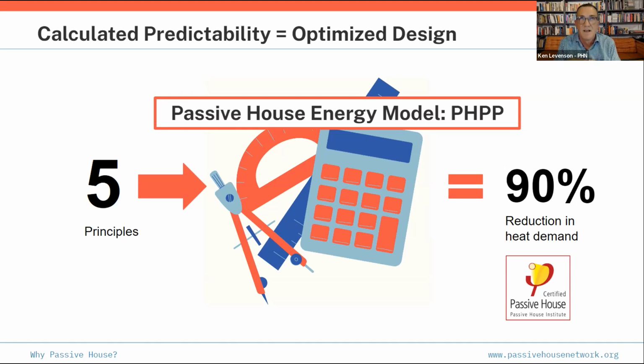We often see the heating and cooling reduced dramatically. When I was practicing architecture, one notable example was a house I was working on in Brooklyn Heights. All the neighbors had 12 to 15 tons of air conditioning on their roofs, and the Historic Preservation Commission couldn't do anything about them because they were mechanical equipment. We did a calculation for a passive house retrofit of a similar home, and compared to the 12 to 15 tons - these are big townhouses in Brooklyn Heights - we needed 1.5 tons of air conditioning, a dramatic reduction. We ended up installing 3 tons because it just seemed too crazy. You do want some buffer, but what we have is a buffer of 1.5 tons rather than a buffer of 5 tons. That's part of that optimization.